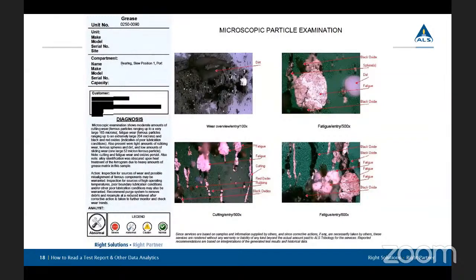I'll share a short story of a situation that we ran into with grease. This is something I personally dealt with years ago in Phoenix. There was a mine that was doing analytical ferrography, and on one of their components, we had done ferrography just like this that showed there was cutting wear. You can see some cutting wear here. There are these long stringers, as it cuts into the metal, it creates these long stringers. They really didn't feel like it was possible for the system. They did their investigating, and they really didn't understand where that cutting wear came from.